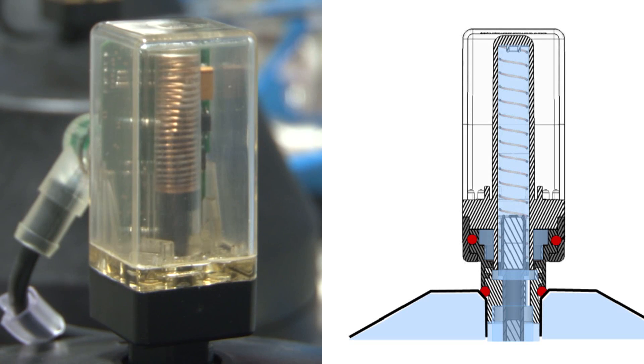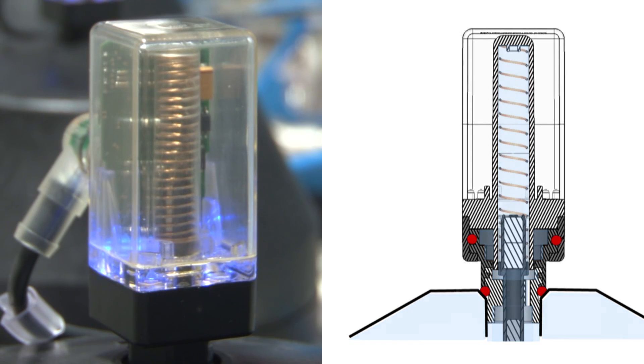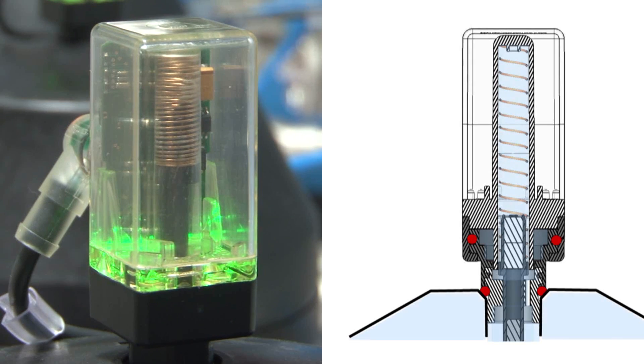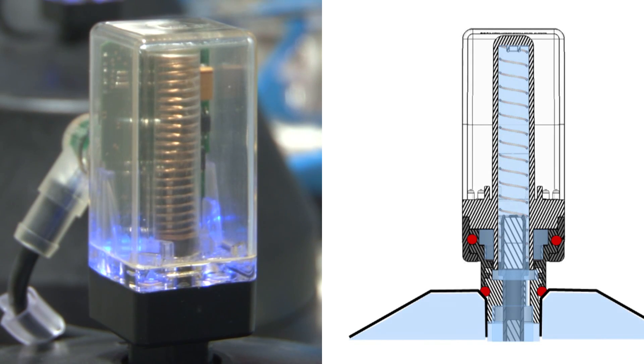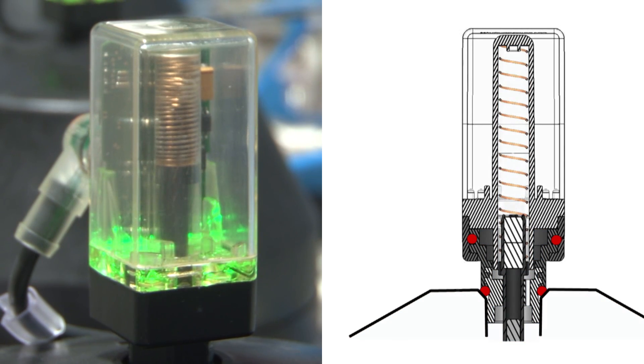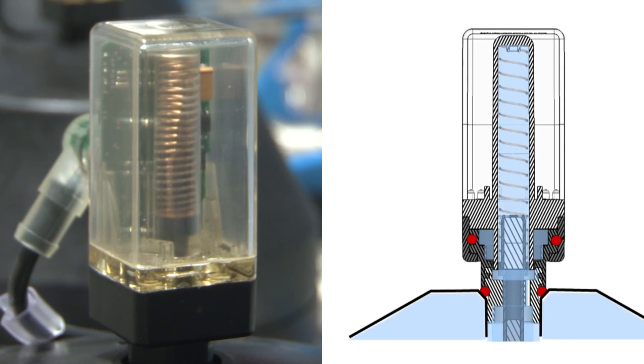The electronic components are hermetically sealed and separated from the mechanical parts. As a result, the area with the mechanical parts is designed to be pressurized and does not need any dynamic sealing. No longer will you have the sealing problems for fail-safe open or double-acting actuators as in the past. This is the advantage of the limit switch working contact-free.